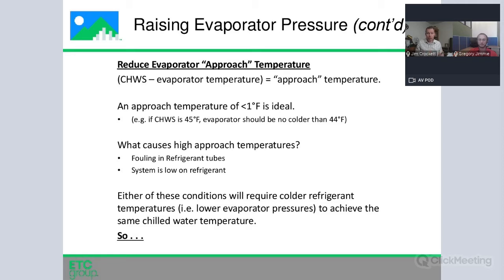So there's a couple of things that can cause your approach to deteriorate. One of them is fouling in the refrigerant tube. Think of it as gunk or buildup happening on the inside of the heat exchanger, the heat exchanger barrel of your chiller. The second thing that can happen is if your system is low on refrigerant. If your system is low on refrigerant, there's less mass flowing, and so to get the same amount of cooling, it has to flow at a colder temperature. So two things that you can do if your system is low on refrigerant: add refrigerant.